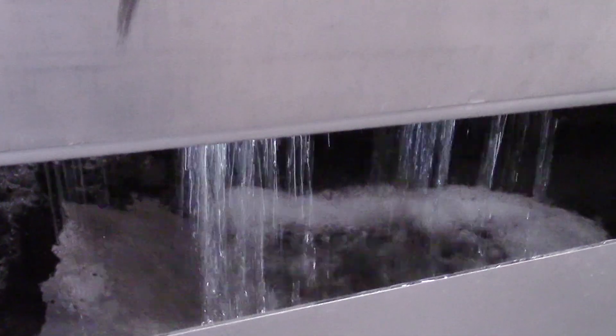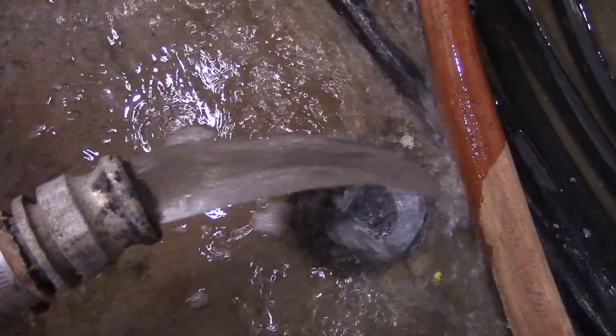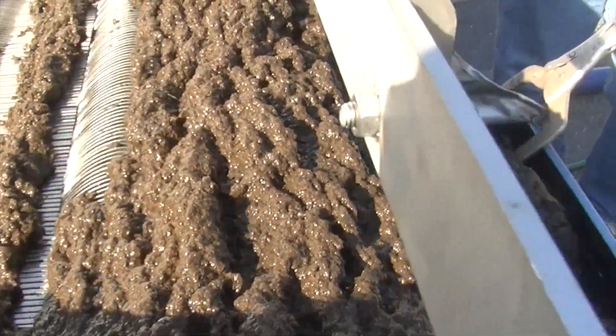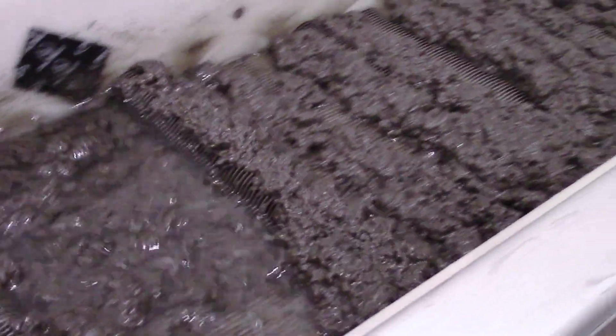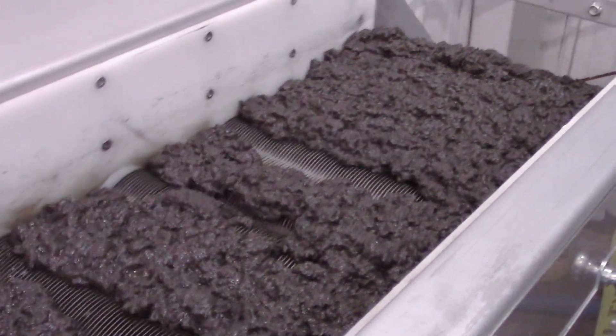The filtrate is captured in the tank below the platform and can be discharged or recycled back to the plant headworks for further treatment. The process material is now thickened to a range of 5–8% total solids, and reduced by about 90% of its original volume. The thickened material is ready to be discharged to the anaerobic digester, or can be further dewatered by a Trident multi-disc press.